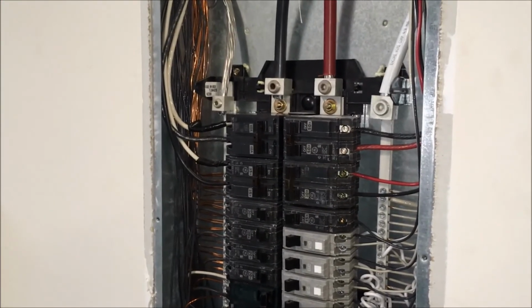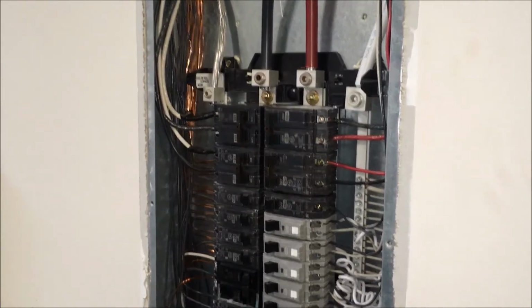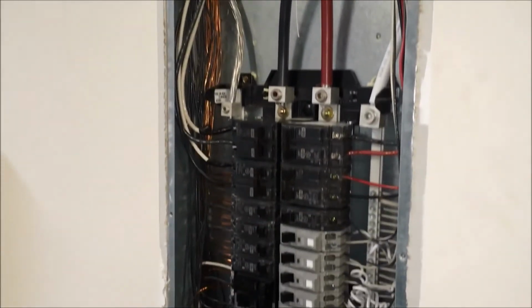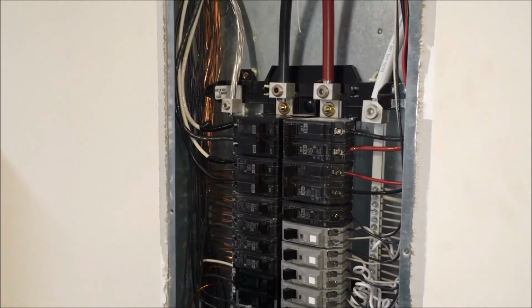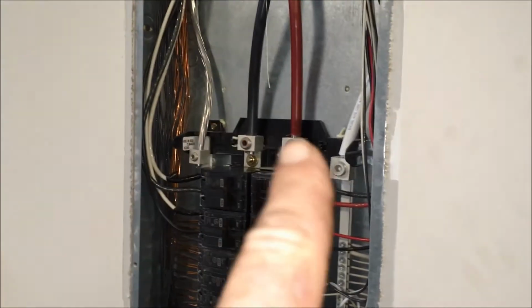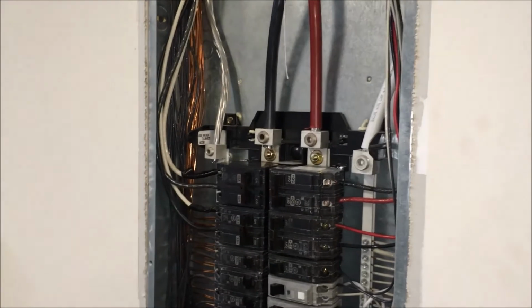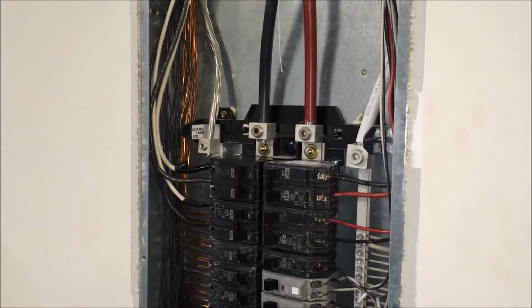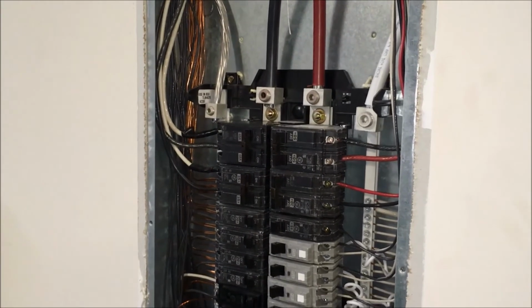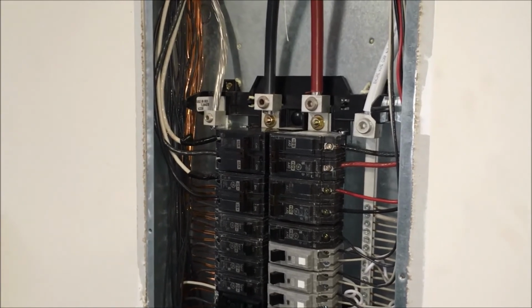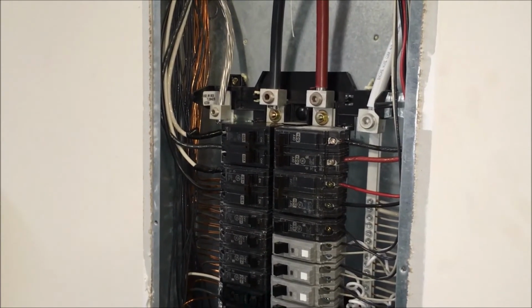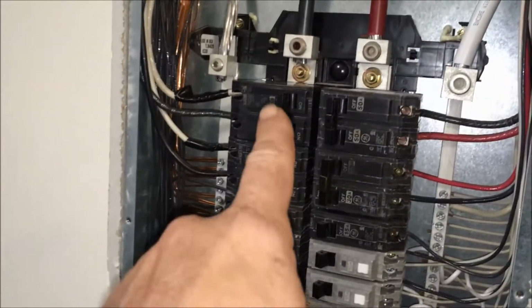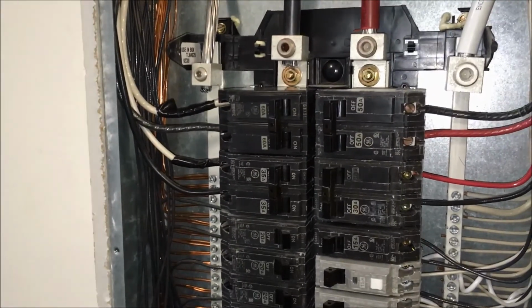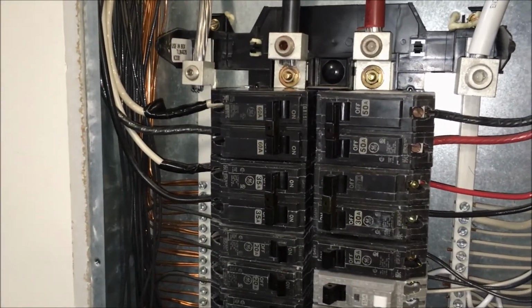First thing to check, obviously, is to make sure that the breakers weren't tripped, and they weren't. Second thing, I removed the panel to expose these breakers. Now, this is very dangerous. There's a lot of exposed voltage. You can see these two lines here. That's 220, 240. You definitely don't want to get close to those. You touch that, you're going to turn into popcorn. But I checked these two breakers, and they tested good, so the breakers were not a problem.